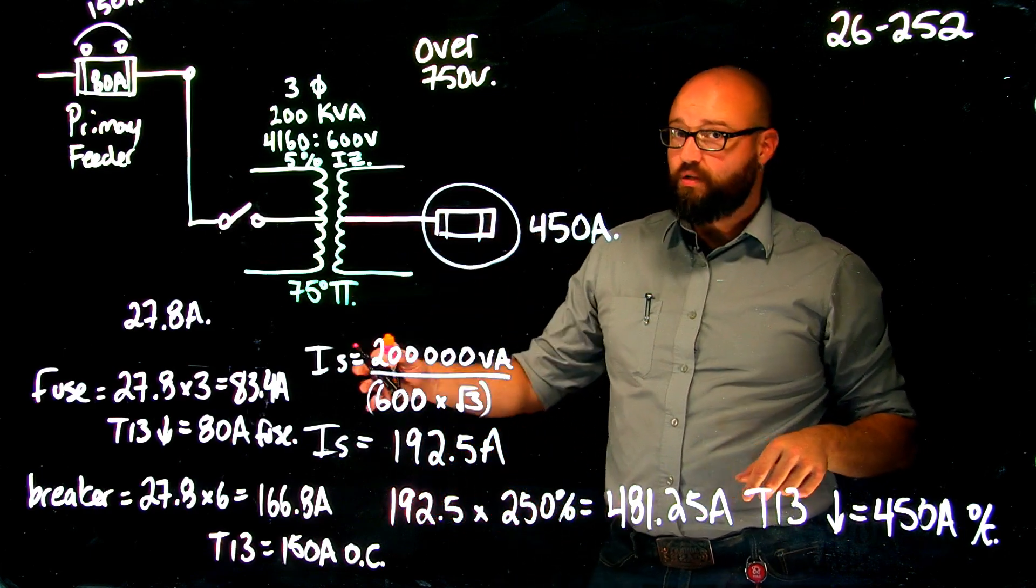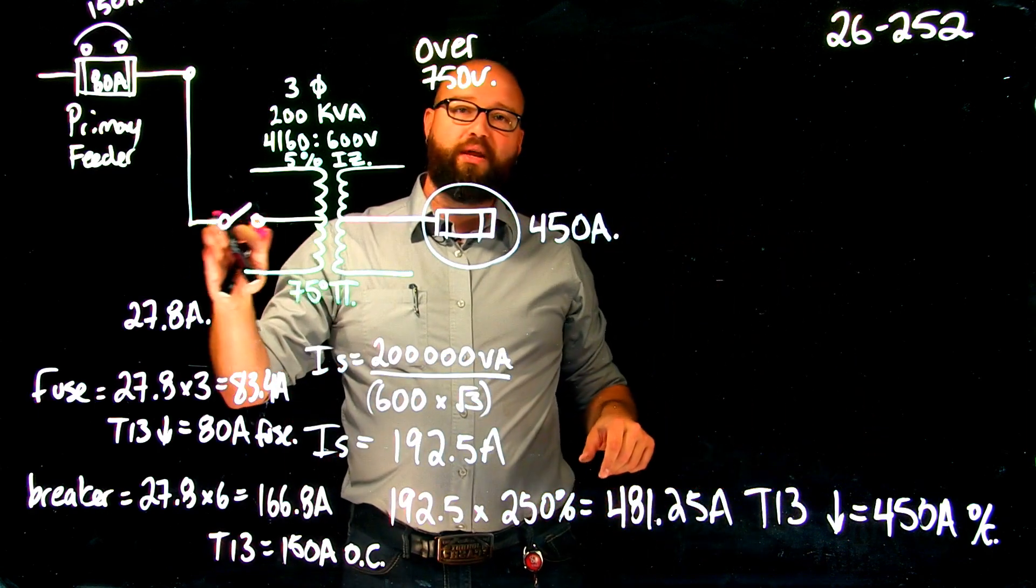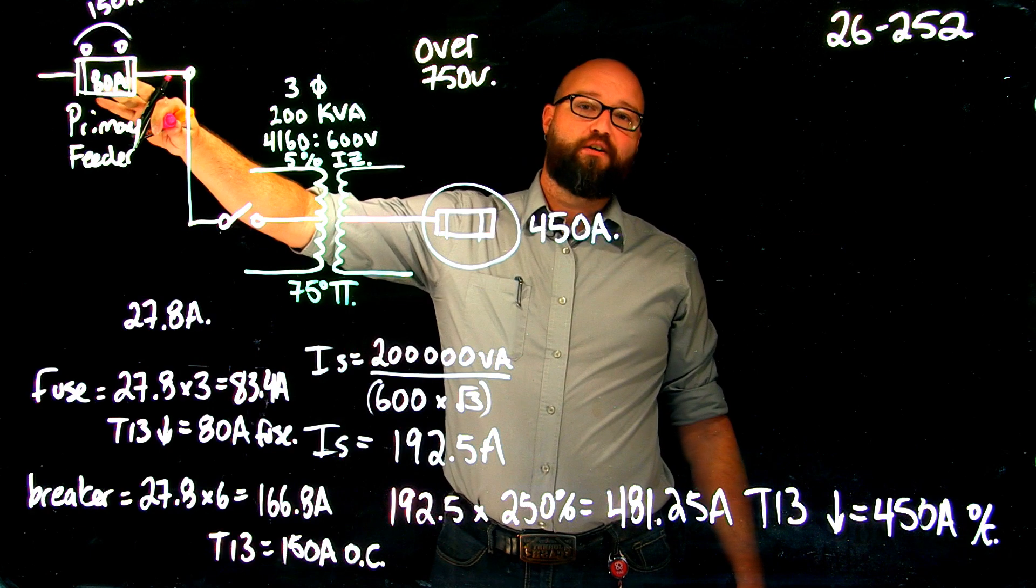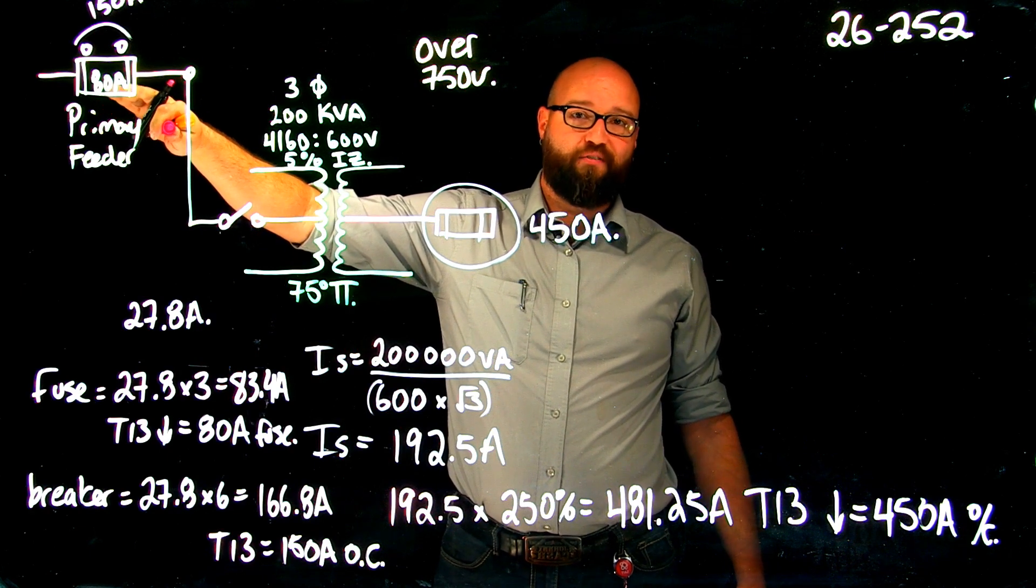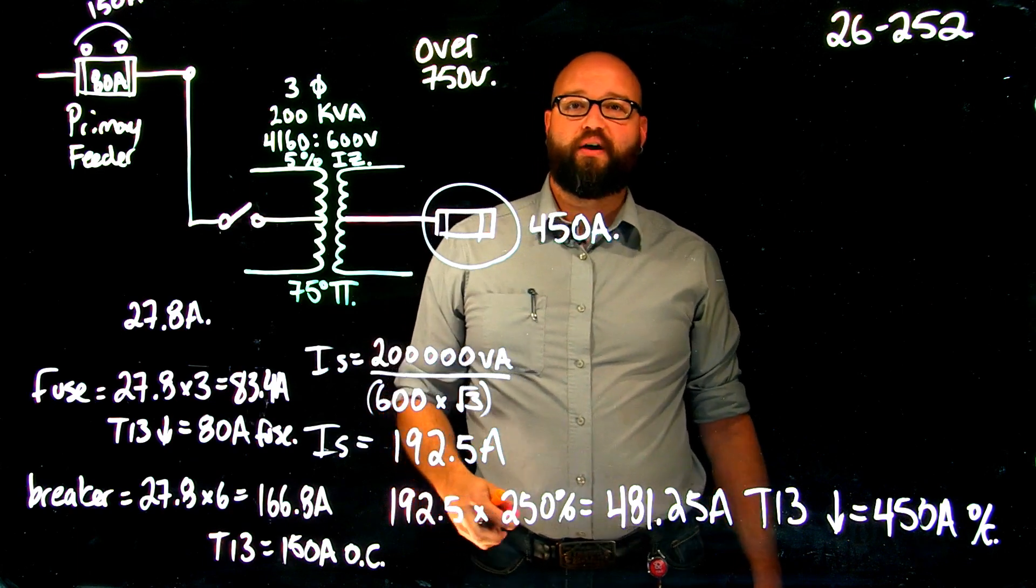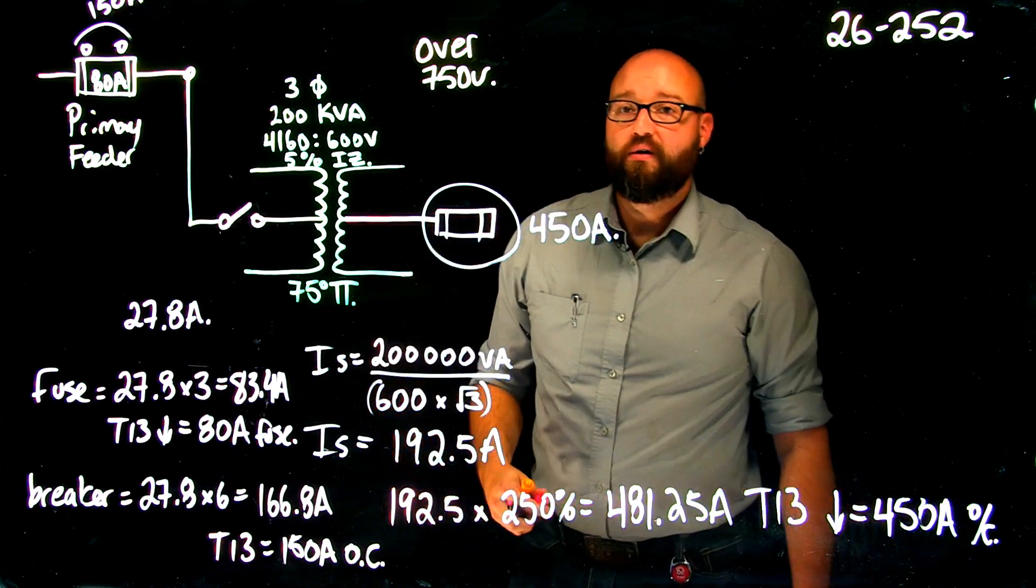Either one of those combined with this 450 amp secondary protection would allow me to omit primary overcurrent. Because I'm omitting primary overcurrent, I must select my primary feeder overcurrent based off the values in table 13, and I must have a secondary overcurrent that is selected based off the values in table 13 as well.